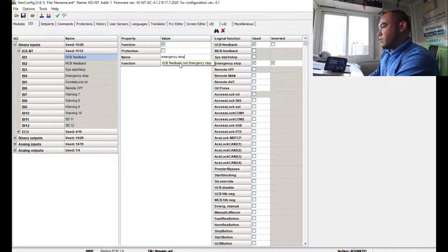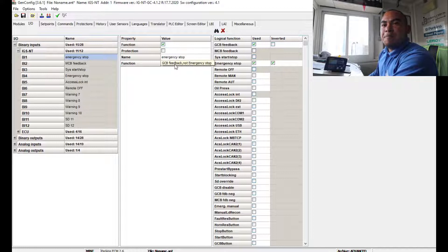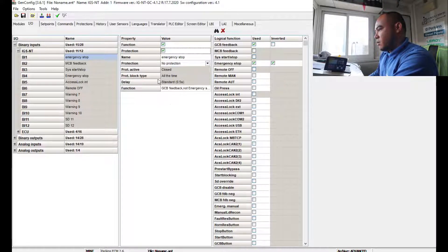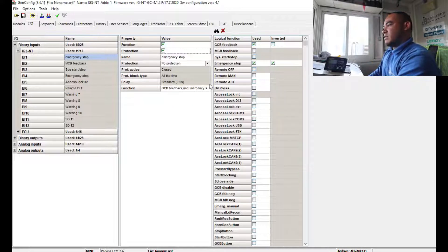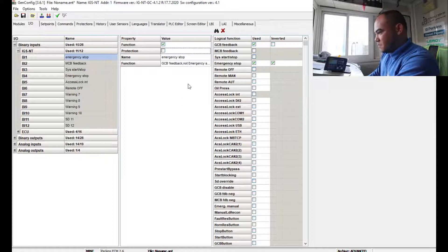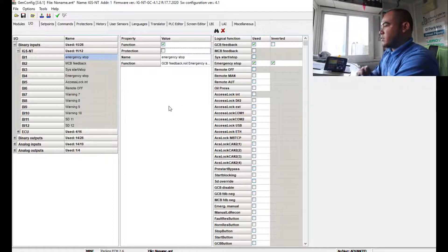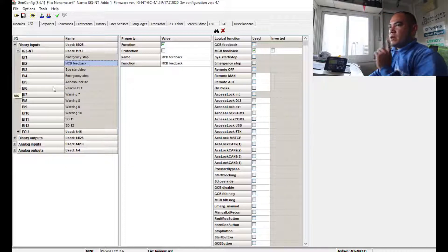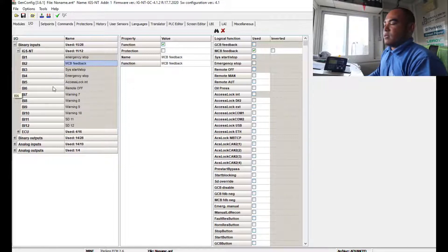For the Emergency Stop function settings, set Function to 'GCB feedback, not Emergency stop'. Leave the protection functions as closed active. There is a 0.5 second delay — since this is a feedback input for emergency stop, just leave those settings as they are.